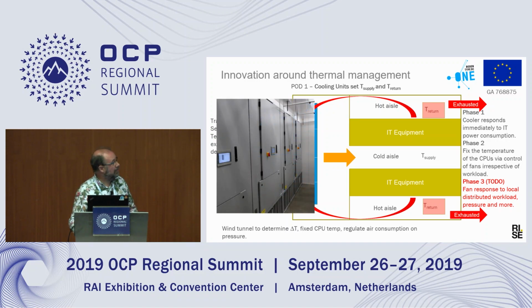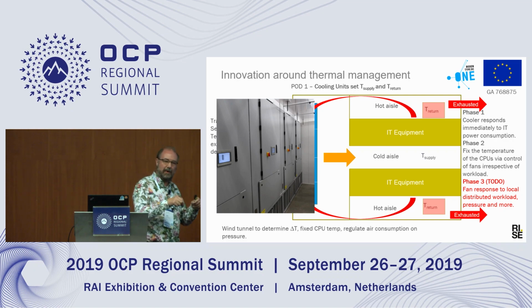These are the cooling units from EcoCooling. Basically, they're just ventilation systems. They ventilate air from outside, and they have dampers which allow us to recirculate air. But they also have wetted pads, which means we can wet the pad and then humidify the air. Now, the challenge in this climate is that if you wet the pad and then allow the minus 30 degrees centigrade temperature to come in over the wetted pads, you freeze them.